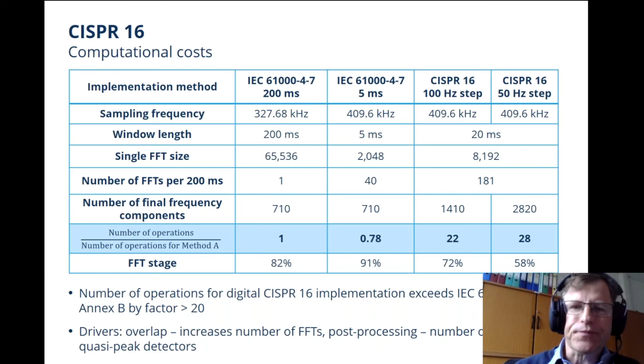Last little issue that I would like to discuss is how to treat long-term measurements. The present methodology below 9 kilohertz for harmonics, or the emission in the frequency range 2 to 9 kilohertz, is that you usually take 10-12 cycles, or the 200 milliseconds, then you do the DFT, and then you get consecutive values of the individual harmonics, as well as integral values, the THD. And then you aggregate it either in the 150/180 cycle, or the 3-second values, and then in the next stage to the 10-minute values.